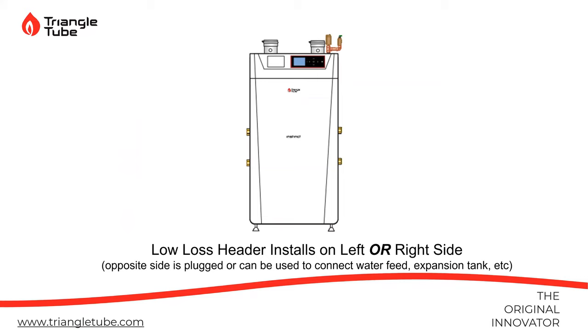The low loss header can be bolted right onto the left or right. If you buy the 110 and the 155, you're going to get a 1-inch separator. And if you go with the 199 combi or heat only, you're going to get a 1.25-inch low loss header. Also, your condensate will be down through here. It'll come out on either side. Your outlet will be located right here. And then there are knockouts on either side for the gas line.